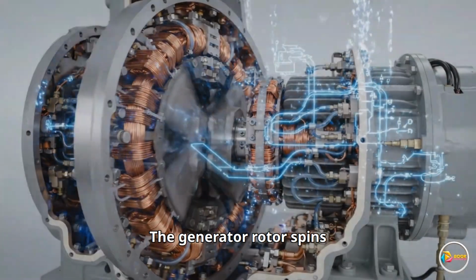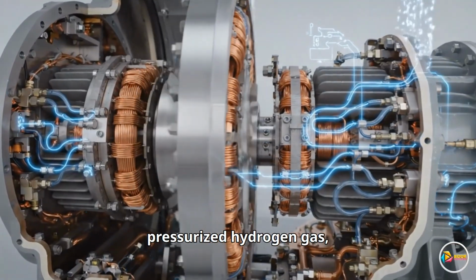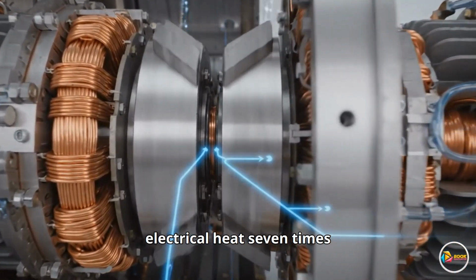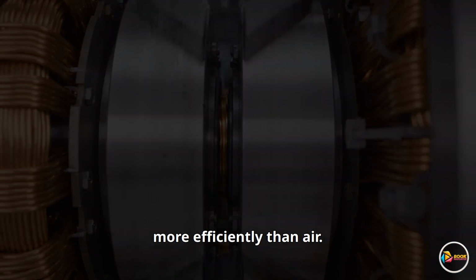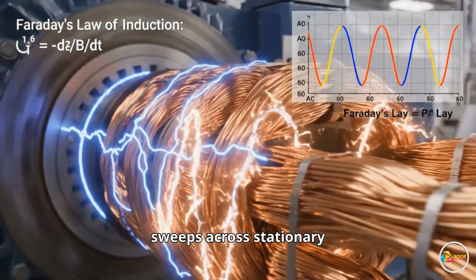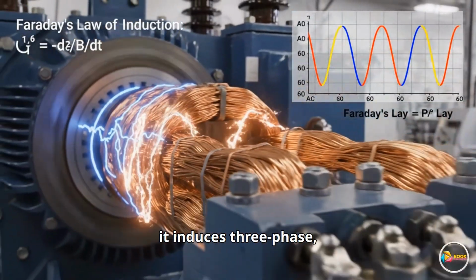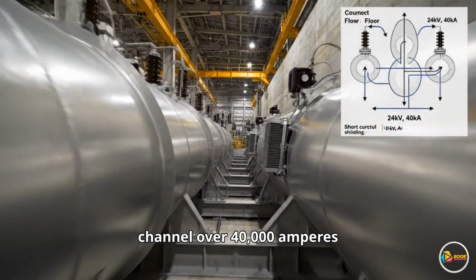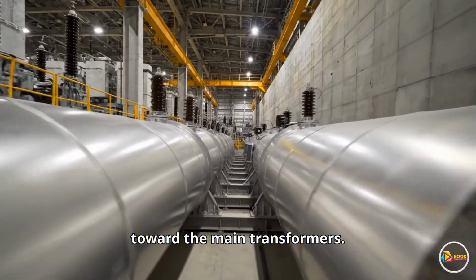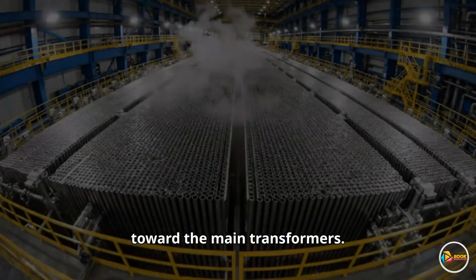The generator rotor spins inside a sealed chamber of pressurized hydrogen gas, which dissipates intense electrical heat 7 times more efficiently than air. As the massive magnetic field sweeps across stationary copper windings, it induces three-phase alternating current. Massive air-cooled aluminum bus ducts channel over 40,000 amperes of current directly through the building foundation toward the main transformers.